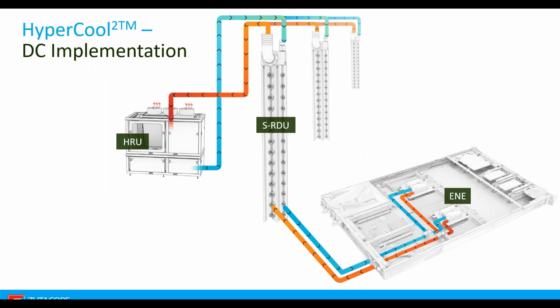So when you look at the system, at the bottom right-hand side, every one of those ENEs, those evaporators, is in direct contact with the chip. It holds in it a very small pool of dielectric refrigerant. We're currently using 3M's Novec 7000, sitting ready for when heat is generated. That translates into two of the system's key benefits: it's instantaneous and it's on demand.